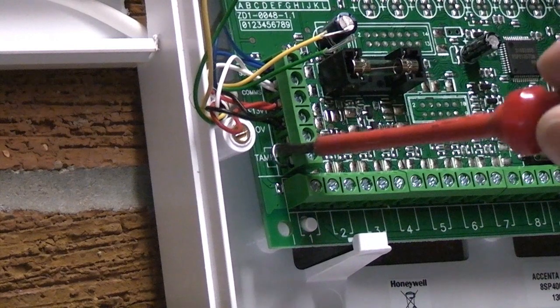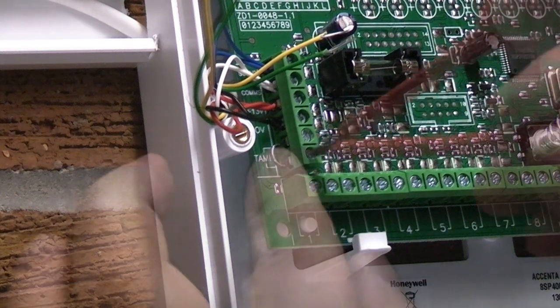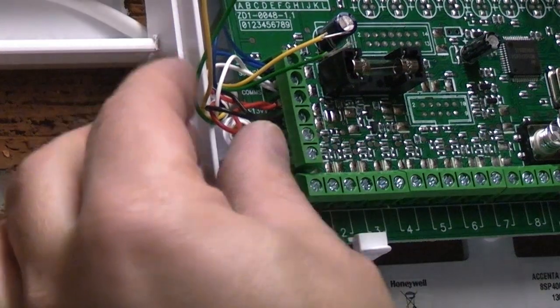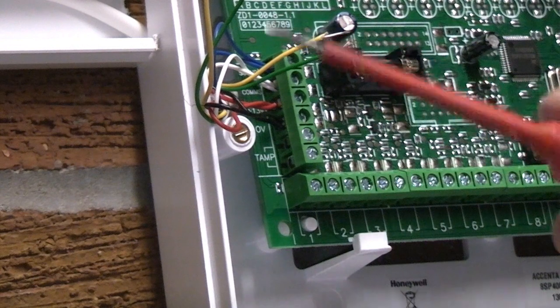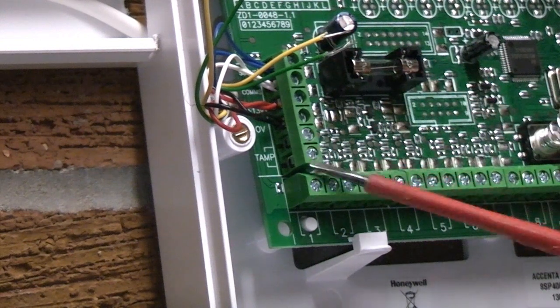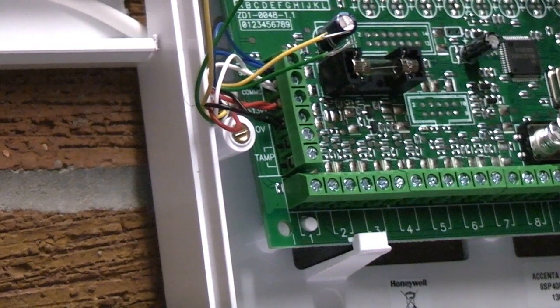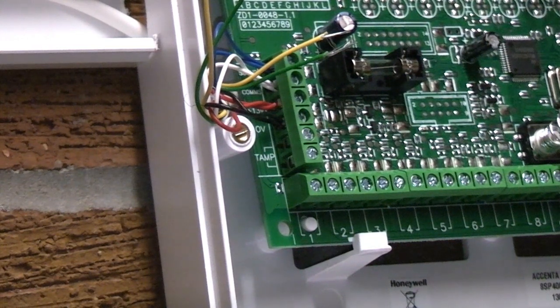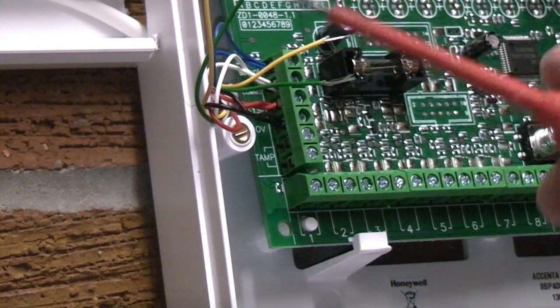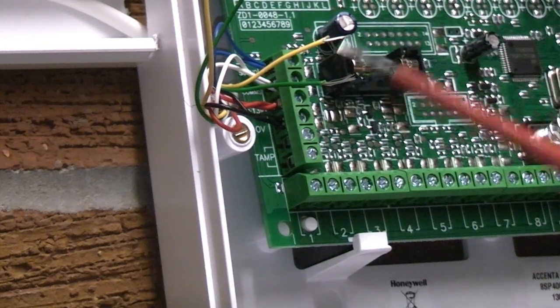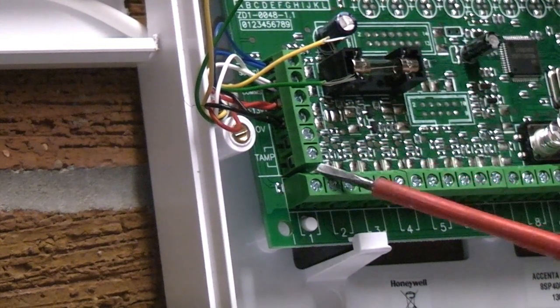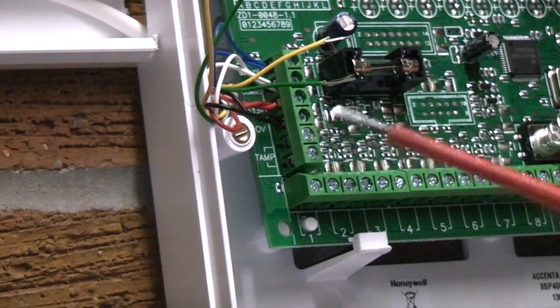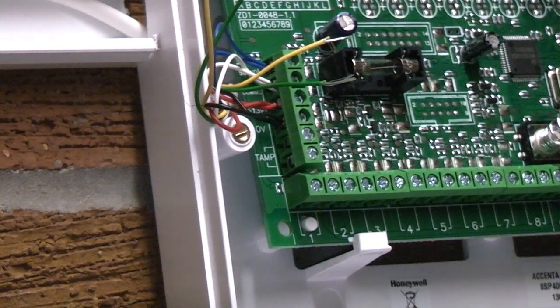If you look at the tamper you'll see that there's a link in there. We need to remove that link. The tamper wires are actually wired in series not in parallel. If you put those four wires into those two terminals, your tamper would never work because you'd always have a closed circuit at one of the tampers. So what we need to do with these four wires is create a loop. We need to connect the yellow to the green and then terminate the green and the yellow into the remaining two terminals. That will give us a circuit. As soon as that circuit is broken, the alarm will go into tamper mode.